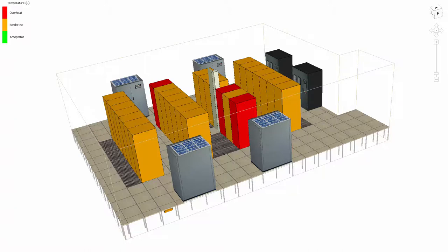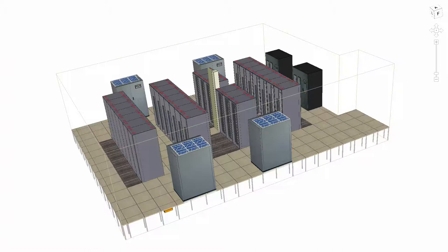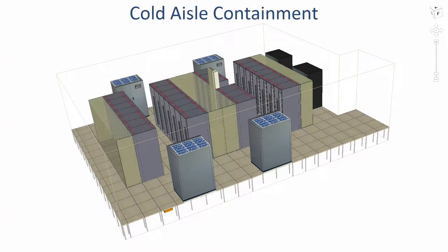One solution could be to set up hot or cold air containment systems. In the cold air contained system, partitions are built to enclose both the floor grills and the equipment inlets. This is done to guide cool air supplied through the floor grills directly to the IT equipment. This system also reduces the mixing of cool and exhaust air in the room, thereby improving the effectiveness of the cooling units.